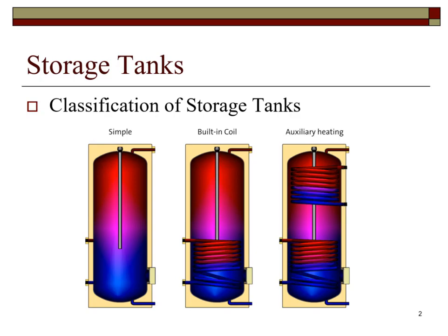The tank on the right has 2 heating elements. One heat exchanger low in the tank to be used the same as the heat exchanger presented in the middle tank, and the heat exchanger high in the tank to be used to heat water with an auxiliary source of heat.